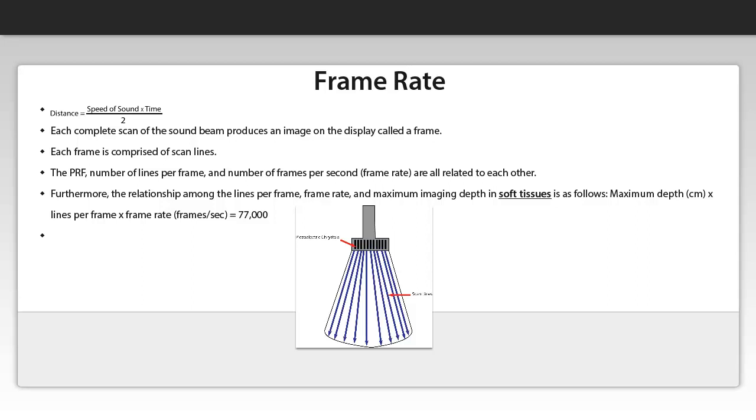Furthermore, the relationship among the lines per frame, frame rate, and maximum imaging depth in soft tissues is as follows. Maximum depth in centimeters, lines per frame unitless number, and frame rate which has the unit of frames per second, equals 77,000.